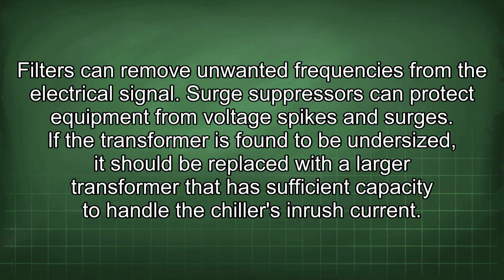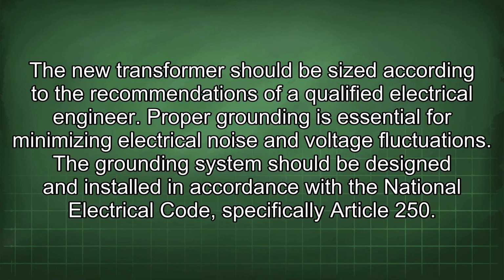If the transformer is found to be undersized, it should be replaced with a larger transformer that has sufficient capacity to handle the chiller's inrush current. The new transformer should be sized according to the recommendations of a qualified electrical engineer. Proper grounding is essential for minimizing electrical noise and voltage fluctuations. The grounding system should be designed and installed in accordance with the National Electrical Code, specifically Article 250.